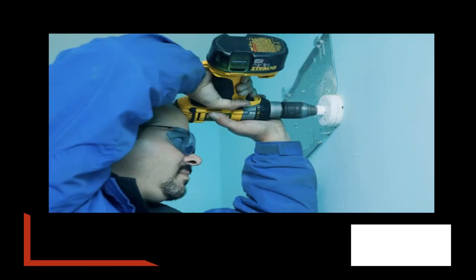Next slide. And then they are making a penetration in your house. The technicians need to run the electrical and refrigerant lines from the outdoor unit to the indoor unit. So oftentimes it's more economical to have the indoor units mounted on an exterior wall. You can certainly put it on an interior wall, but that often involves additional carpentry, and carpentry isn't free. But any penetrations going in and out of the house should be well sealed against moisture, airflow, and any sort of pests that might come through the exterior.